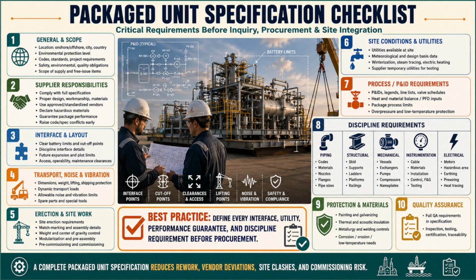Include the approved supplier list, cause and effect diagrams, and any project-specific packaged unit instrumentation philosophy. Provide blank or partially completed data sheets for vendor completion. Do not allow instrument details to remain buried inside proprietary drawings. Define signal types, communication protocols, segregation, termination philosophy, junction box requirements, intrinsic safety barriers, hazardous area certification, shutdown architecture, alarm philosophy, and interface with the plant control system.